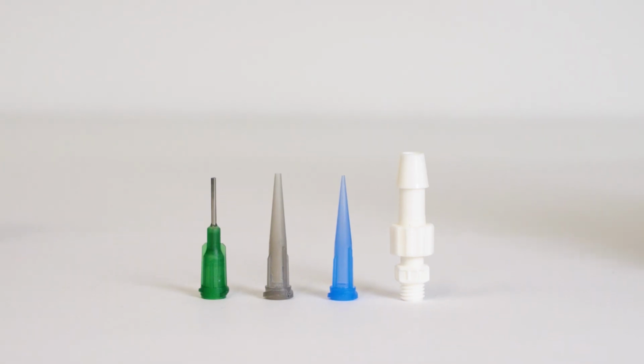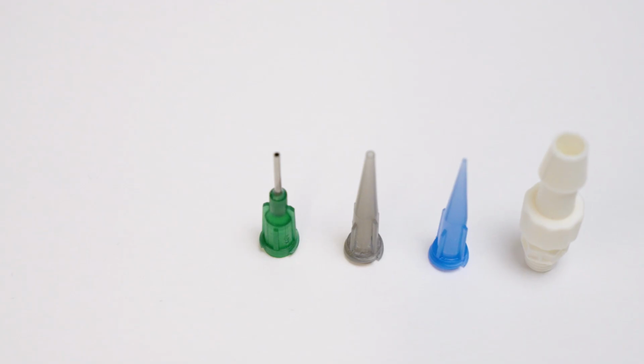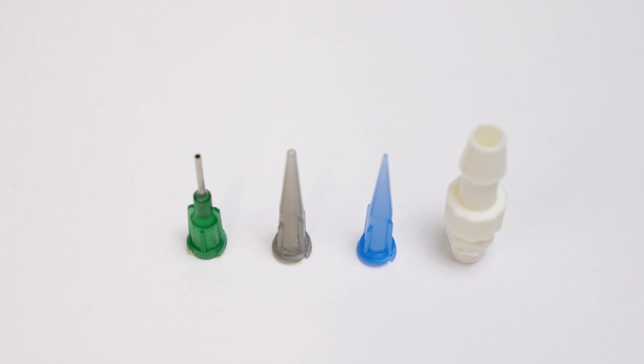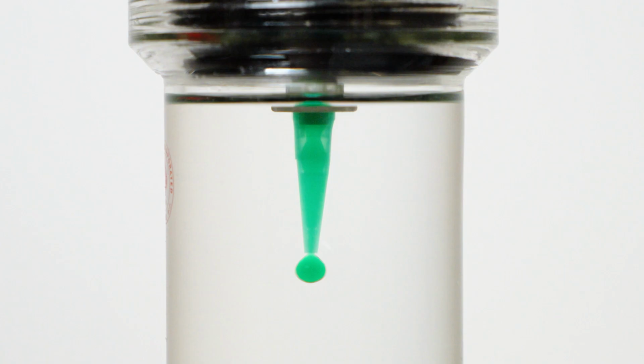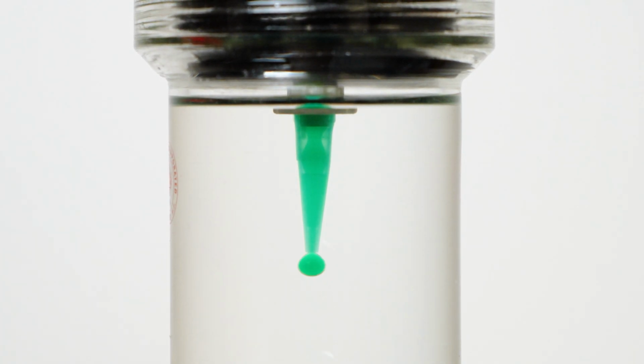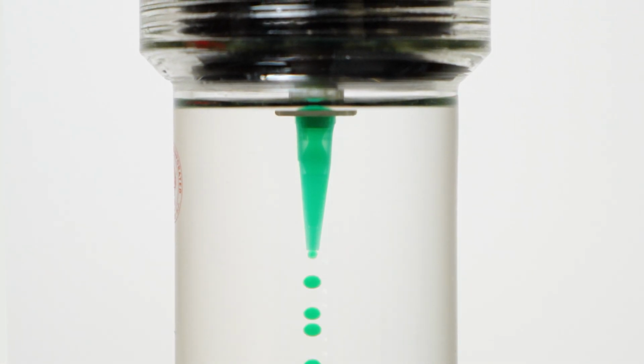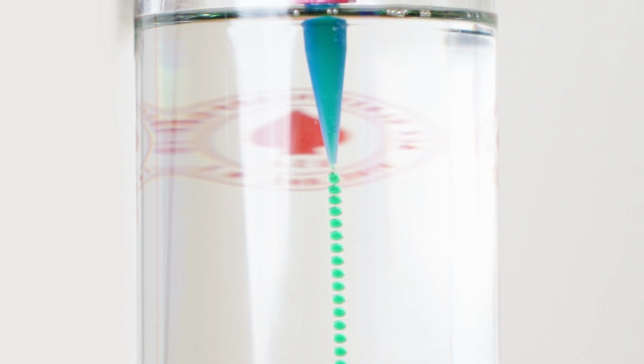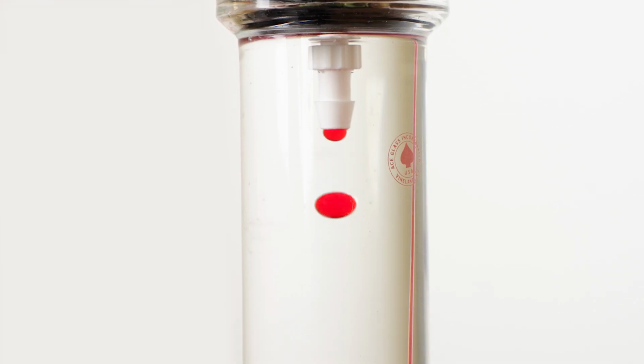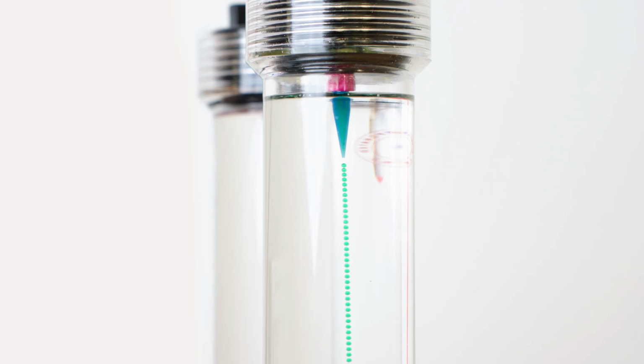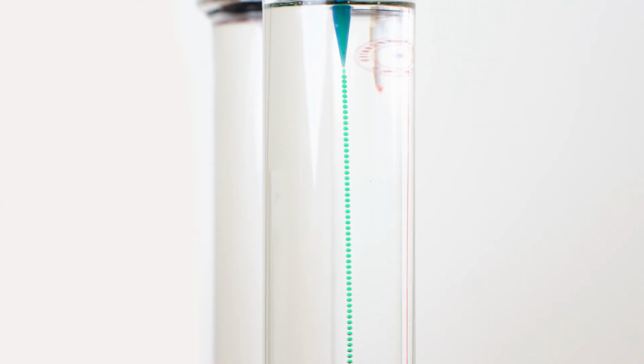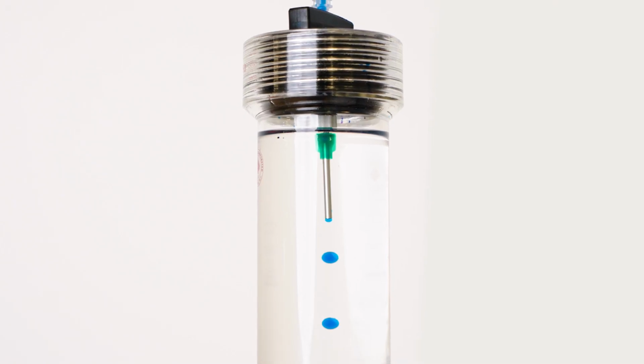The dispense tip significantly impacts your ability to dose successfully. A conical tip geometry is commonly paired with our pumps, as it reduces pressure drop, improves flow control, and enhances droplet detachment. A general rule when selecting tip sizing is straightforward. Smaller internal diameter tips produce finer droplets and are ideal for low volume dispenses. Large internal diameter tips generate larger droplets and are suitable for higher volume applications. Using hydrophobic materials helps prevent residual droplets from adhering to the tip. Making the right tip selection can have a big impact on precision and accuracy in dosing applications.